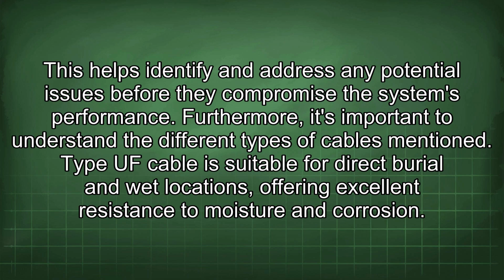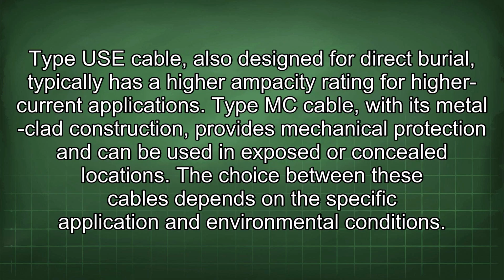Furthermore, it's important to understand the different types of cables mentioned. Type UF cable is suitable for direct burial and wet locations, offering excellent resistance to moisture and corrosion. Type USE cable, also designed for direct burial, typically has a higher ampacity rating for higher current applications. Type MC cable, with its metal-clad construction, provides mechanical protection and can be used in exposed or concealed locations. The choice between these cables depends on the specific application and environmental conditions.